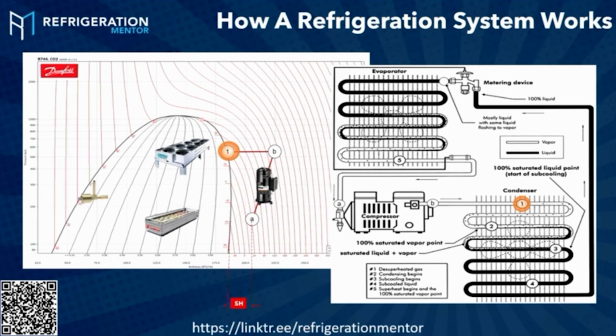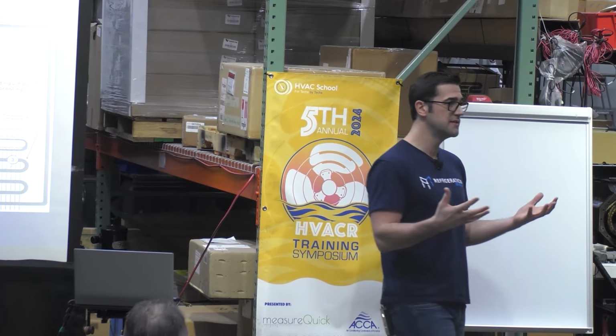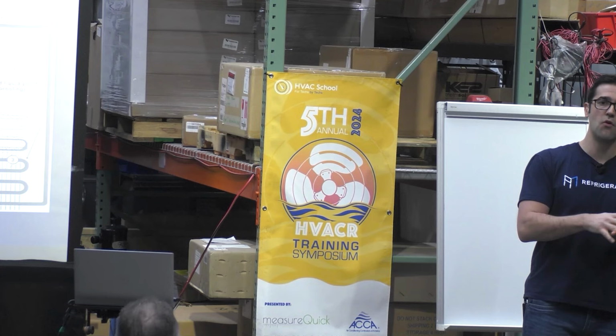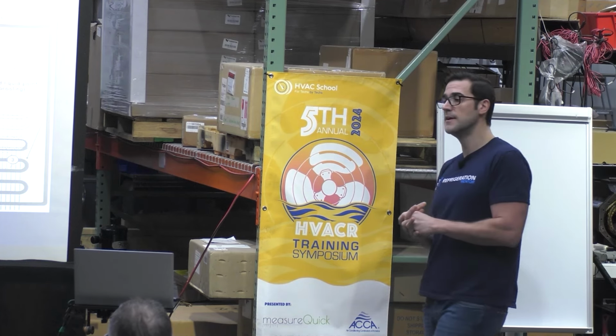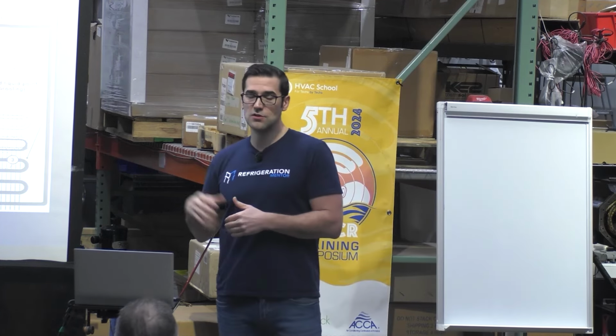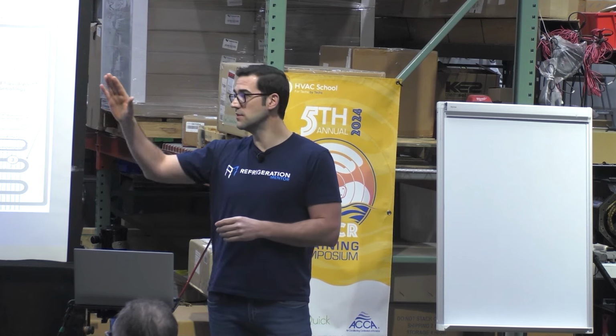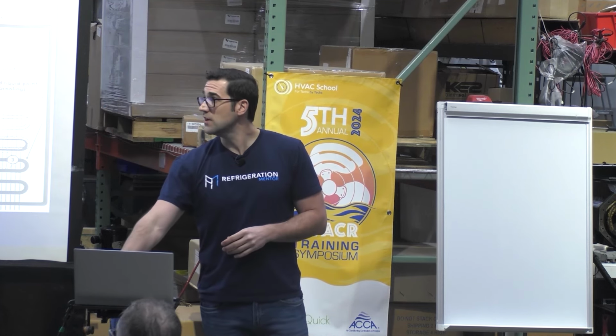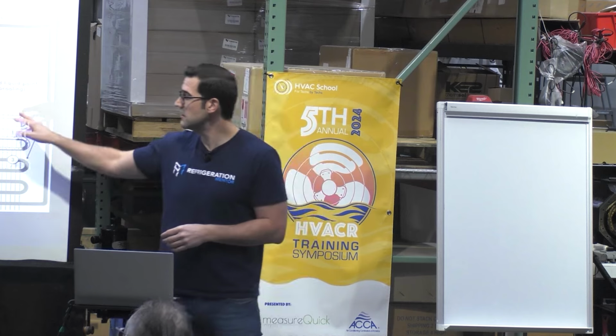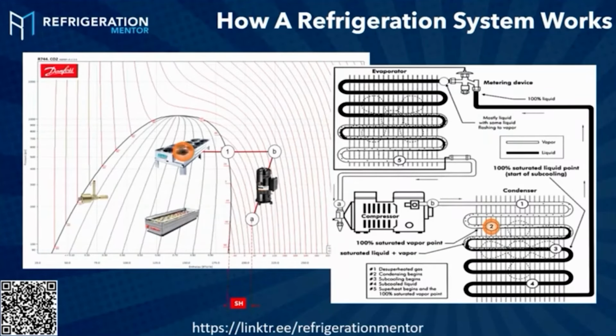The superheat, right? Because when we have a glide refrigerant, like all the new refrigerants are glide, there's blends of refrigerant. It could have 3 or 4 or 5 different refrigerants. You get to that dew point, and then you know it's vapor. So this is your dew point. As you start to travel through the system, you can see here, we start to condense. The condensation starts to begin.